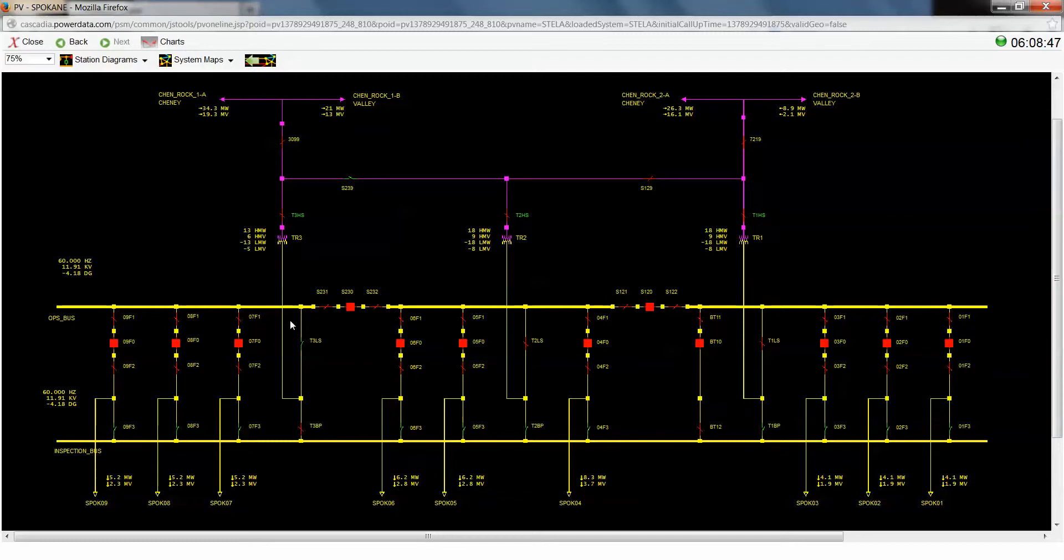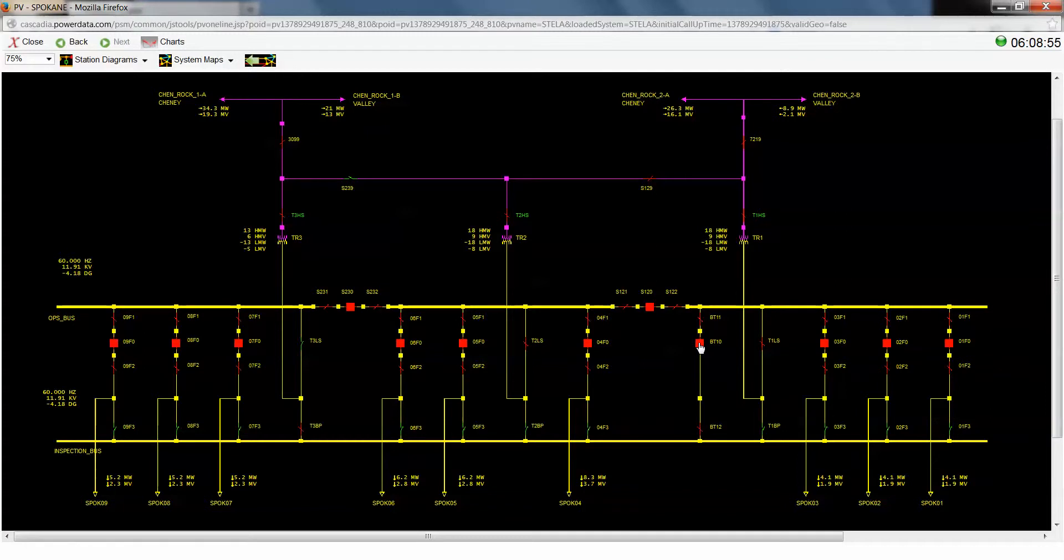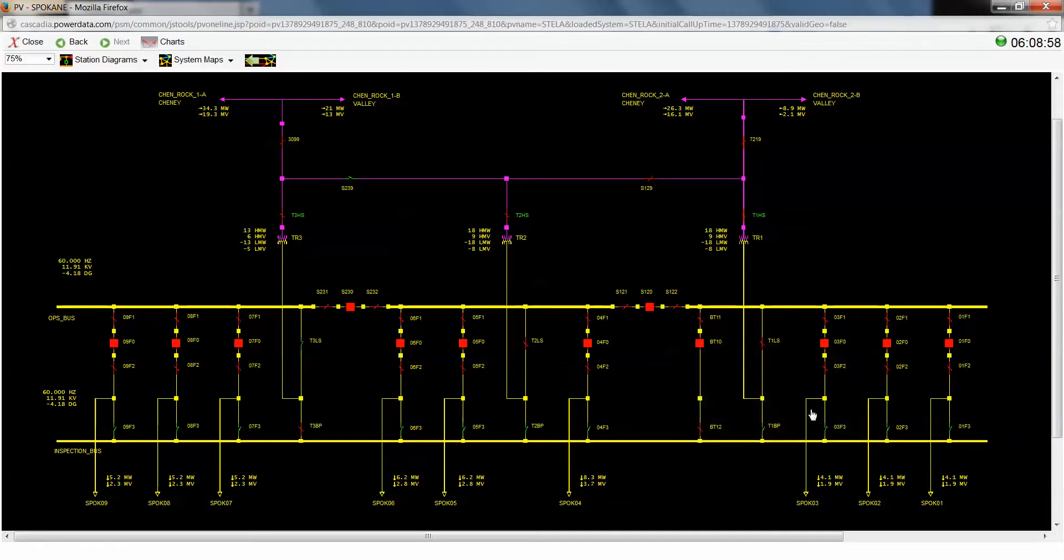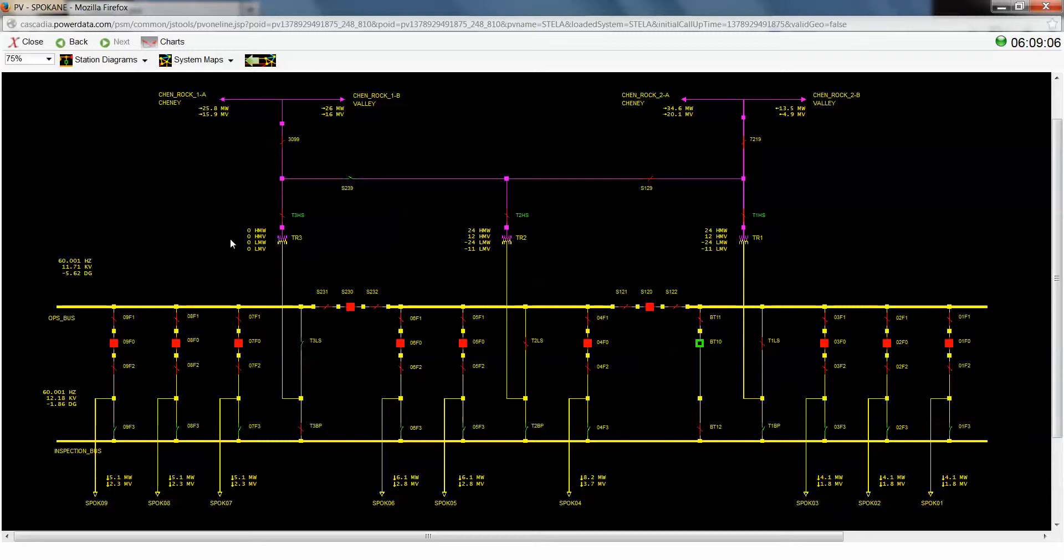So now I see the low side switch of this transformer has come open. Now in order to actually remove the load from this transformer, we're going to reopen our bus tie 10 switch, because you always want to make or break your load through a circuit breaker if possible, since those switches are not actually rated to do that. And now you'll see our transformer three is unloaded.